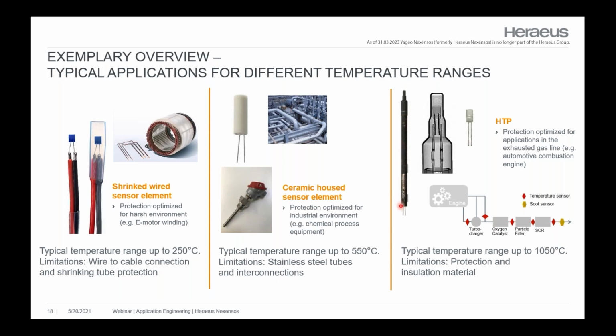And if you have these connecting wires here, they are protected in the tube with mineral insulation, which is really special to handle. But this is the only chance to withstand 1000 degrees with good enough electrical insulation.